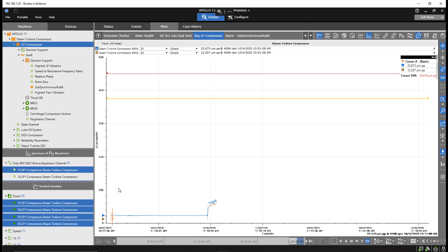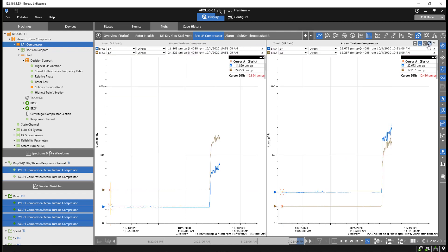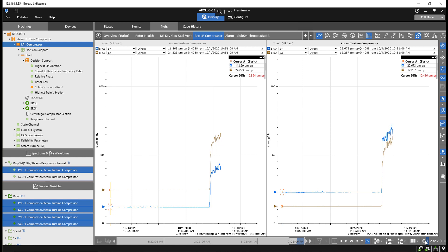After reviewing relevant information captured by System One, including vibration information, bearing metal temperature, and radial position of the shaft, the engineer agrees with the decision support detection of the rub condition and concludes the rub is related to misalignment between the turbine and compressor due to a thermal transient condition.